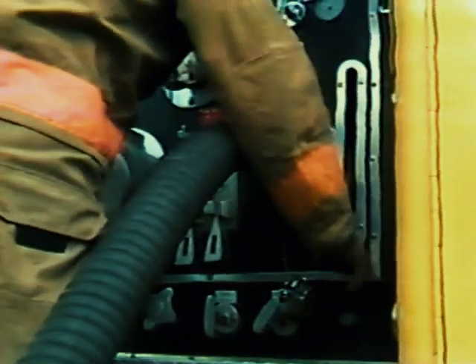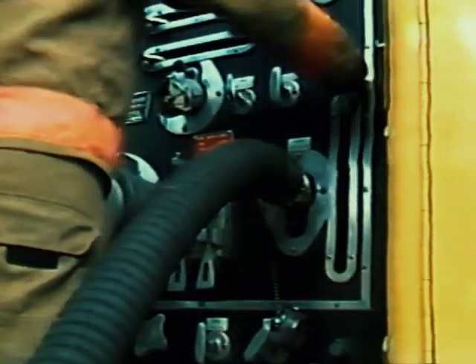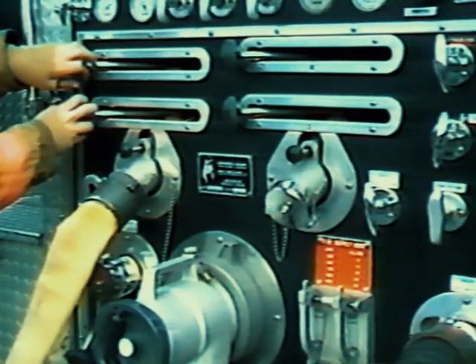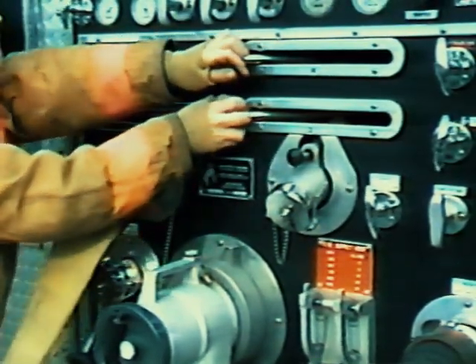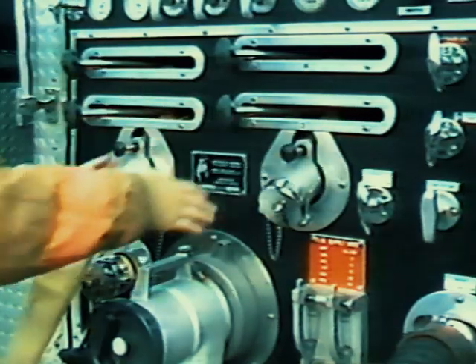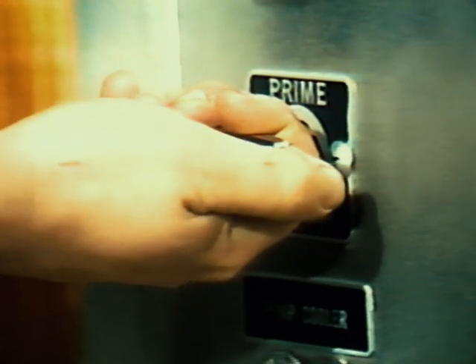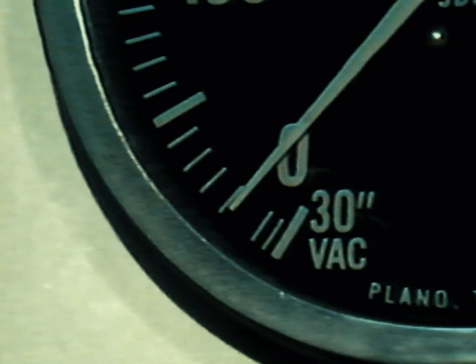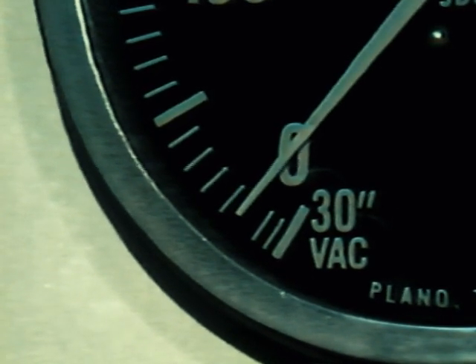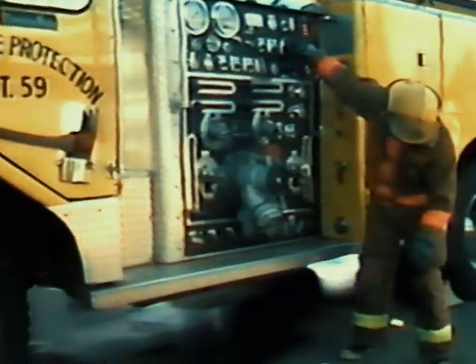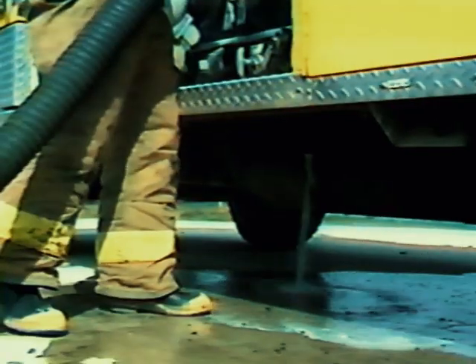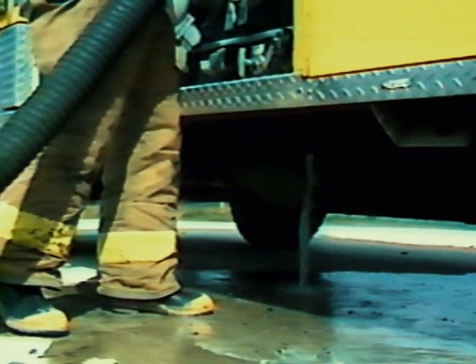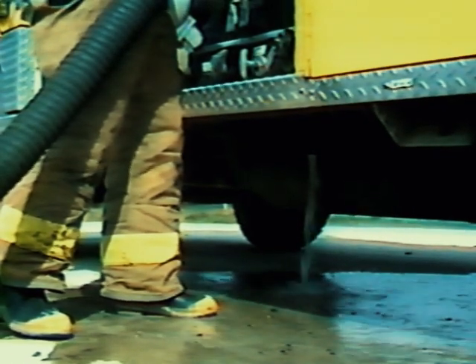To operate the priming device, first, open the intake valve you are going to use for suction. Next, make sure all other valves and openings of the main pump are closed to form an airtight chamber. Use the priming control and activate the priming system. Watch the vacuum gauge to see that a vacuum is being formed, and wait until water flows from the priming discharge valve, indicating that water has reached the pump. Do not shut off the priming device too soon. During the initial stage of priming, there will be air escaping with the water from the primer discharge.